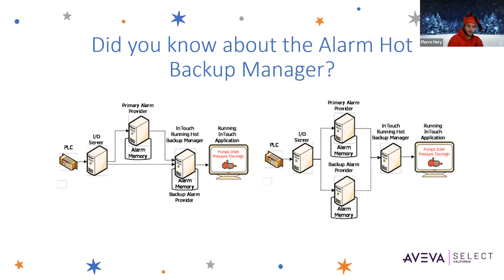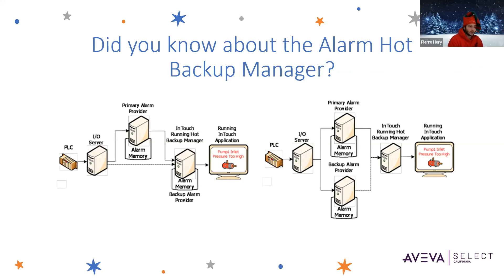You can use the Alarm Hot Backup Manager's configuration utility to create a duplicate alarm provider. Here you have two configurations shown on this screen. On the left, you can see the Hot Backup Manager and the Backup Provider on the same node. But on the right image, you can see that you can also use a schema where the Hot Backup Manager uses a secondary current alarm repository as a backup provider.